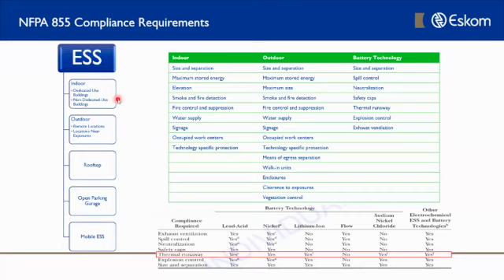You need to be very careful where you position whatever you're building, whether you're outdoor and remote, or near other exposures - very important. On a rooftop, open parking garages, the standard gives guidance depending on where your system is located. Indoor, outdoor, specific size of the system, elevation, whether you have fixed fire protection, water supply, whether the area you're placing it in is occupied, etc.